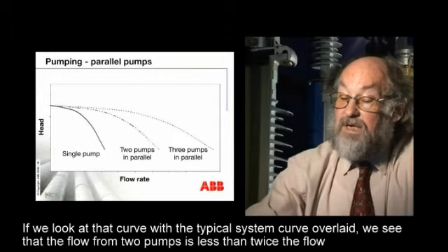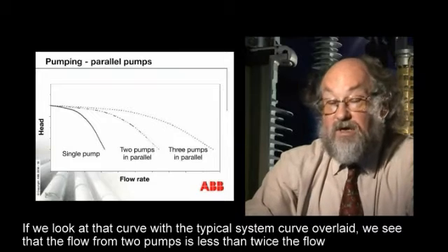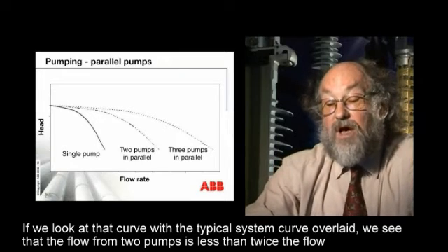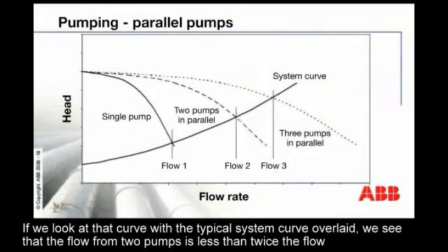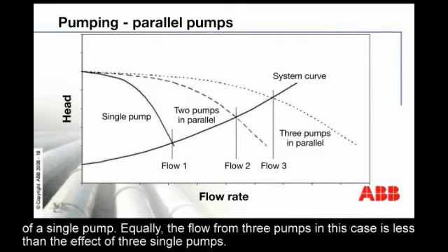If we look at that curve with a typical system curve overlaid, you can see that the flow from two pumps is less than twice the flow of a single pump. Equally, the flow from three pumps in this case is less than the effect of three single pumps.